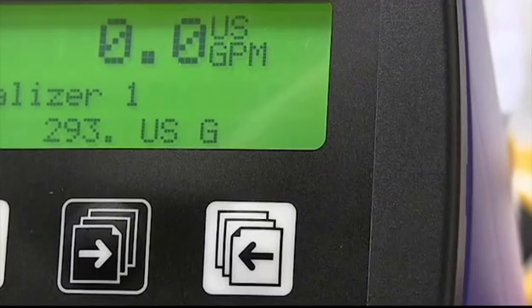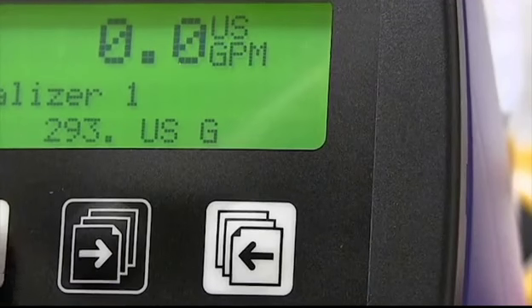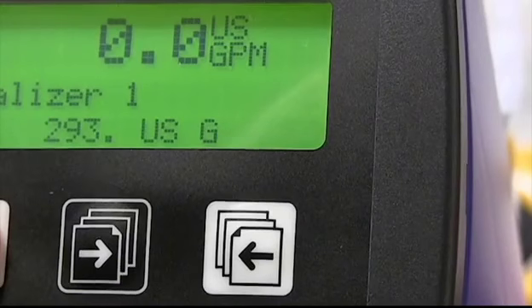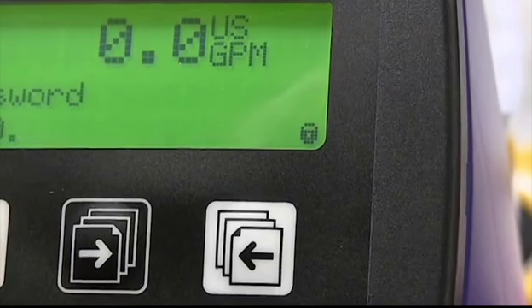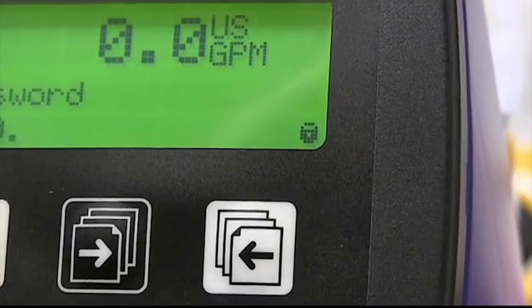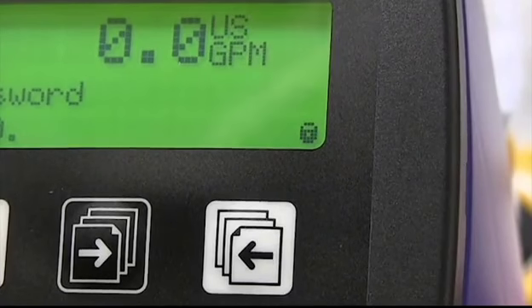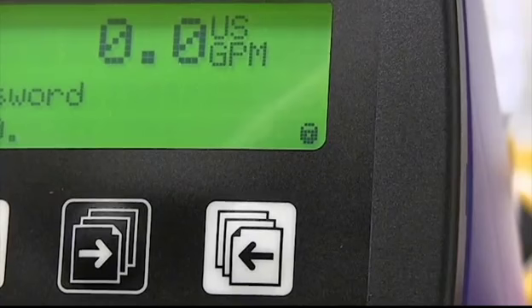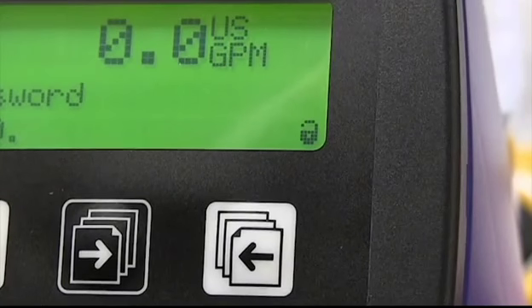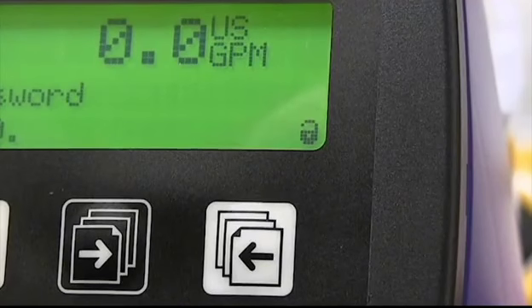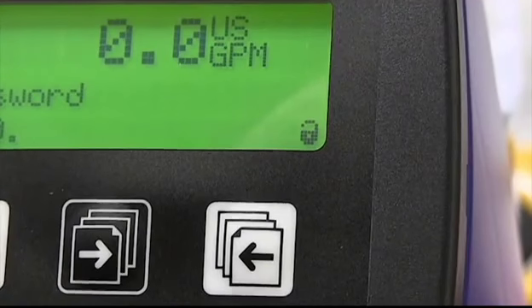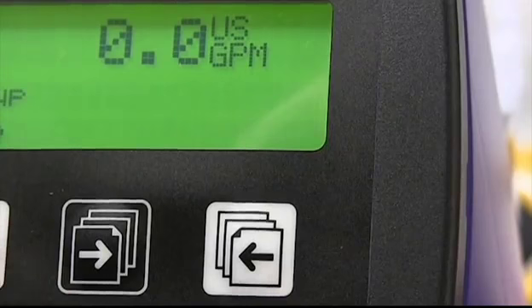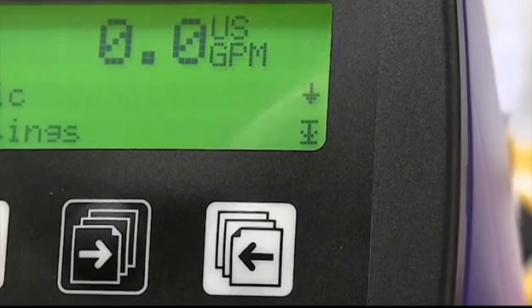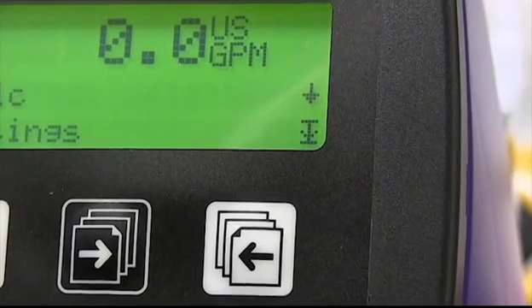So you want to press the upper left hand button, this one here, and hold it in for 2 seconds. It's going to come back and ask you for a password. Now that password is 1000. That's a default for this transmitter. Press the button directly below that 2 times and it will read 1000. Press the lock unlock 1 time and it goes into setup mode, and then quickly changes to basic settings.